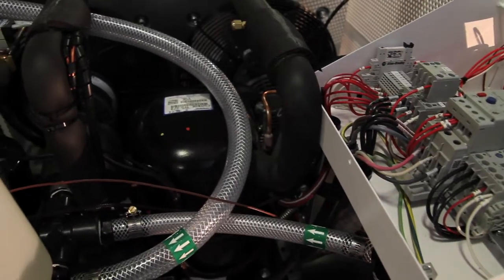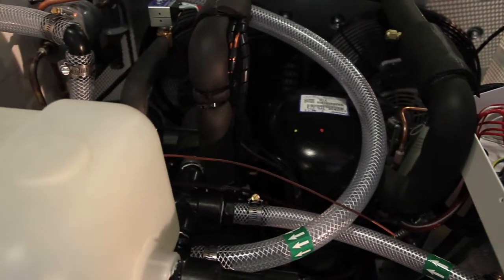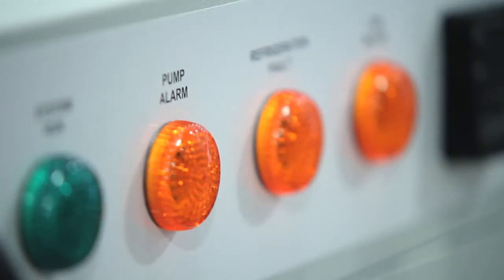The corrosion in the system can really affect more than just the chiller. If it gets inside the customer's process, it can affect their cycle rates or whatever they're using the process for. They also have biological issues that happen within closed-loop systems — algae and other bacteria that can form. They sought out several chemical companies to come up with a formulation that would solve the corrosion process, which is fundamentally dissimilar metals.